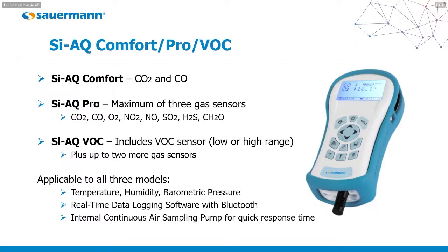As you can see on the screen, we offer a couple different ranges for the VOC sensor. We have a low-range sensor, which measures from 0 to 20 ppm, which is the equivalent of 20,000 ppb. That's typically used for most indoor air applications. We also offer a high range that can measure as high as 200 ppm.